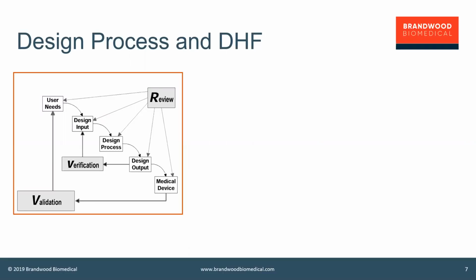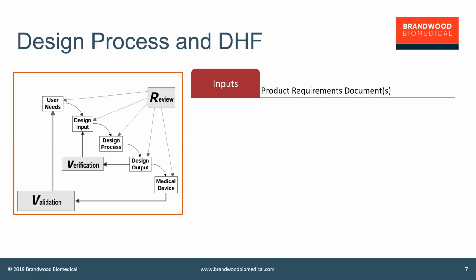Again, this is to describe the overall process of design and development, from user needs to inputs to process to outputs and to an actual completion of a medical device, with how it's tied into verification and validation. If we think about input specifically, we're talking about the product requirement documents. Those documents that describe the requirements of your product to meet not only the user needs, but the overall intent of your product.